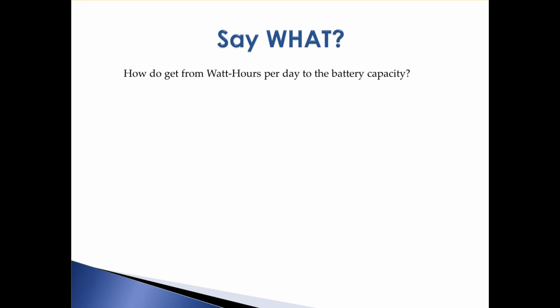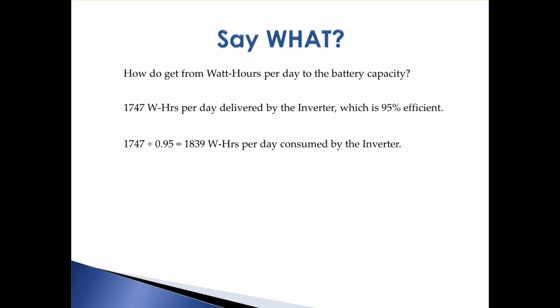How do you get from watt hours per day to battery capacity? We know we have 1747 watt hours per day delivered by the inverter, and the inverter is 95% efficient. So we divide 1747 by 0.95, which gives us 1839 watt hours per day consumed by the inverter, or drawn from the battery. If that's at 12 volts, it might be slightly higher, but we'll use 12 volts. That gives us 153 amp hours per day required from the batteries to meet the needs of our energy audit.